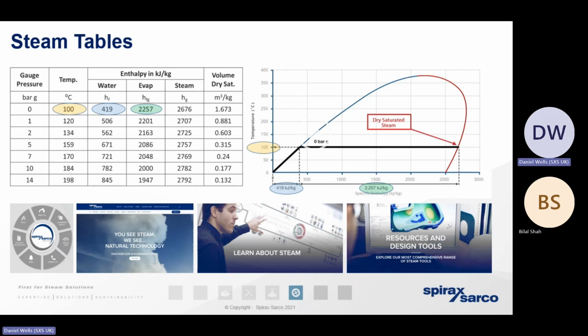And if you look at the bottom axis on the graph here, that represents the energy content. In other words, the wetter the steam, the less energy the steam has. So there's a double whammy going on here. We've got a reduced mass of steam available as a result of the heat loss in the pipework, and the steam that is available, it's got less energy. So that tells us that either the heat exchangers are now undersized and the process time is going to extend, or the boiler's got to work even harder to produce even more steam. So our cost of steam, our cost of gas, and our carbon emissions are going to escalate further still.